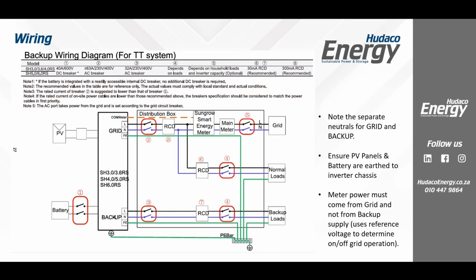On the installation, now this box here, please note, is not representative of a single distribution board. Okay, it's very important that we understand that it's not a single distribution board, but it could be multiple DBs. It could be in 1 DB, but in South Africa, you might want to separate into 2 or 3. And of course, if the inverter is somewhere far away from the DB, it might even be a third one. We've got the grid feed coming in. Then we've got a main breaker, right? And then often a main meter. Now, sometimes in South Africa, this meter will sit on this side, just depends on the property itself and how it looks. But this would be the Eskom or municipal meter, or whatever meter it is that's reading the energy on the property.